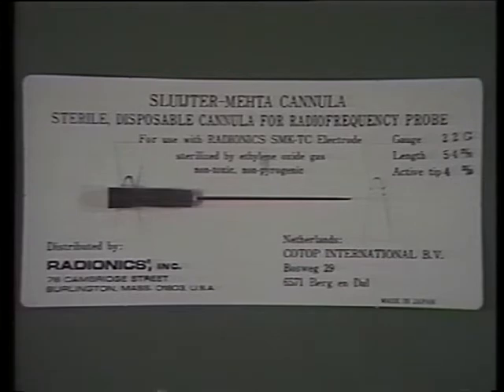There are 2 different types of electrode systems that one can use in the cervical area. The short 6-centimeter version of the SMK system offers the advantage of temperature monitoring. However, the cannulae are introduced very close together, and it's difficult to keep the cannulae in position while taking the radiofrequency probe in and out during the procedure.